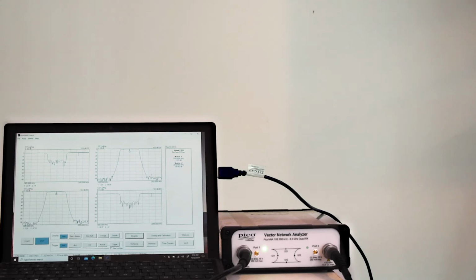For general use, fast speed, about 90 decibel dynamic range, set calibration bandwidth to 1 kHz. Set calibration power to 0 dBm. Leave bandwidth set to 10 Hz during the measurement. For best dynamic range, set calibration bandwidth to 10 Hz. Set calibration power to +6 dBm. Leave bandwidth set to 10 Hz during measurement. In all cases, calibration averaging should be set to none.